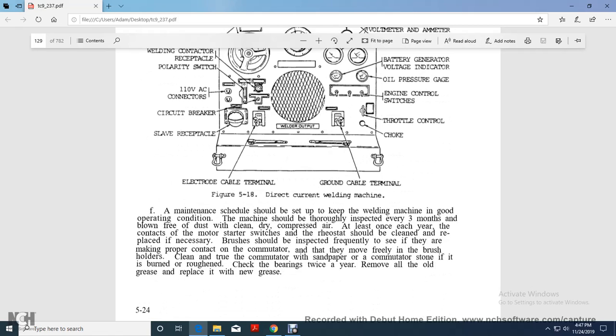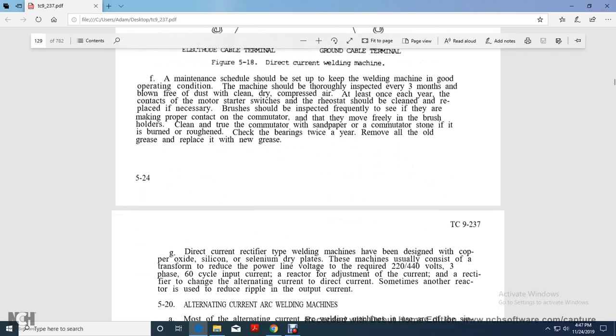A maintenance schedule should be set up to keep the welding machine in good operating condition. The machine should be thoroughly inspected every 3 months and blown free of dust and dirt with dry compressed air. At least once every year, the contacts of the motor starter switch and rheostat should be cleaned and replaced if necessary. Brushes should be inspected frequently to see if they are making proper contact with the commutator and moving freely in the brush holders. Clean and true the commutators. Sandpaper the commutator if it is burned or roughened. Check the bearings twice a year. Remove all old grease and replace it with new grease.